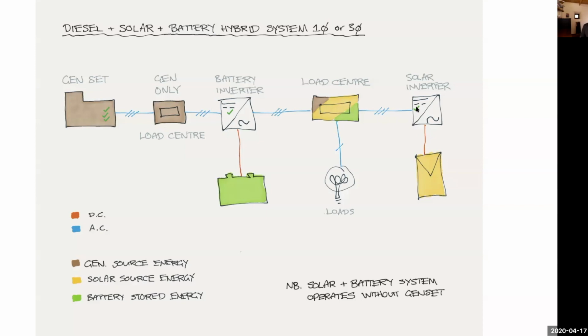But Craig, I know you're an experienced installer, you probably know generating sets aren't as reliable as solar inverters or solar panels - there's always a reason they won't start. They've run out of fuel, the maintenance regime is insufficient, they've failed, the start battery has gone flat because it hasn't run for so long and there's no trickle charge on it. All of those things can mean your generator doesn't start, and this can be quite a big deal, often meaning a call out for the installer to kickstart the system. But as Craig alluded, a simple solution is a small DC coupled system that connects in and can directly charge that battery independently of the generator or the solar inverter.